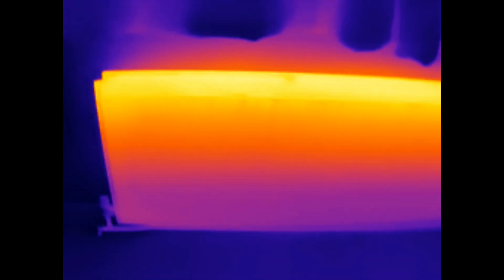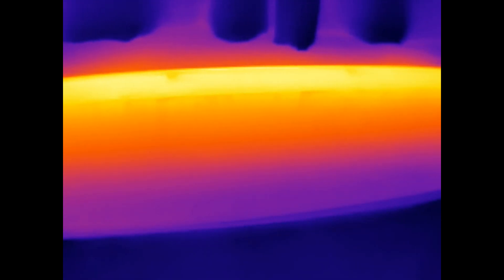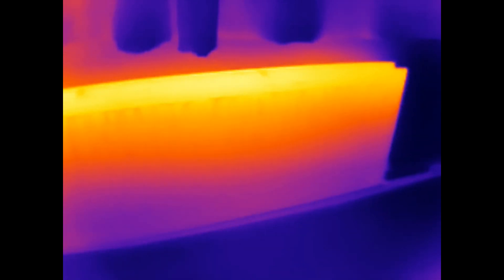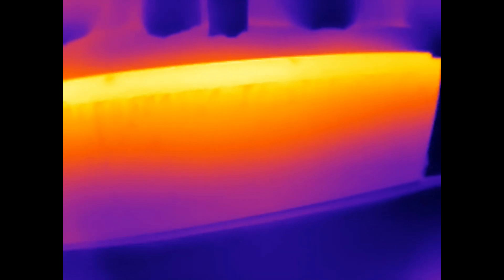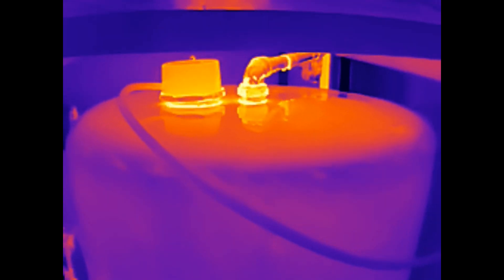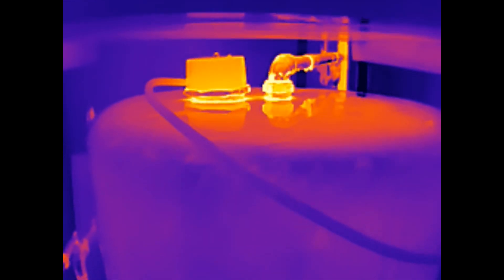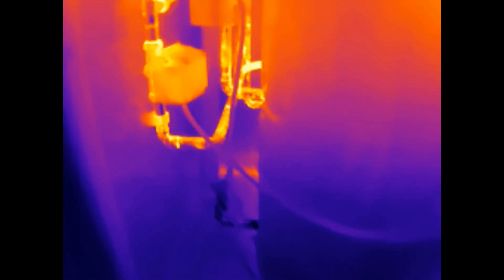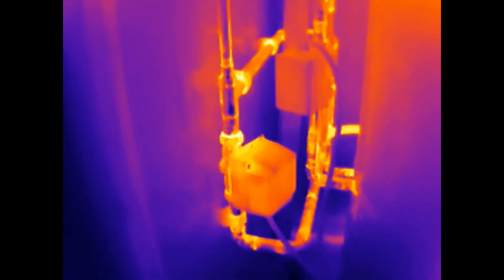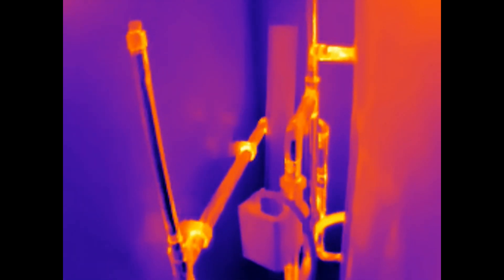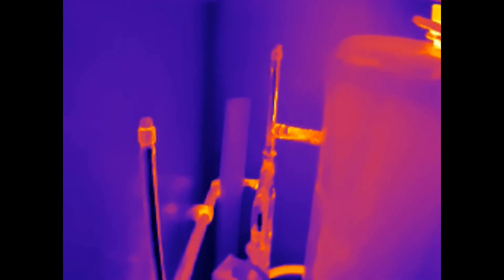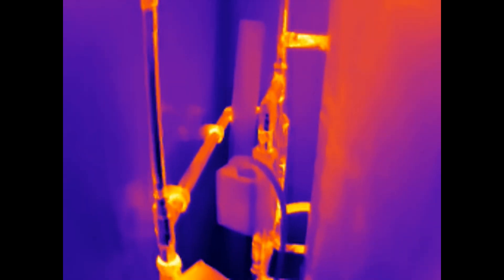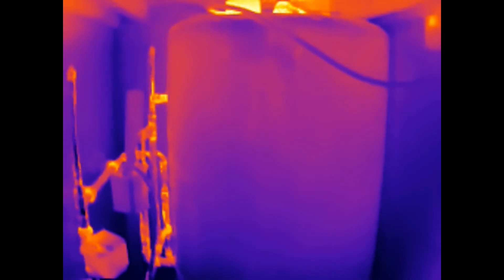We can move inside the house. Heating and plumbing is another great application for these devices. If you examine your heating or water pipes, you can see where the heat is going or not going. Looking in my airing cupboard at my hot water tank, we have this lagged with an insulation jacket and you can see that's doing pretty good. The heating pipes to the side carrying hot water up into this area are hot because they're metal carrying hot water, and you can see those as the glowing areas. But if we look at the water tank itself, it's not as hot, so it is keeping the temperature in quite well.